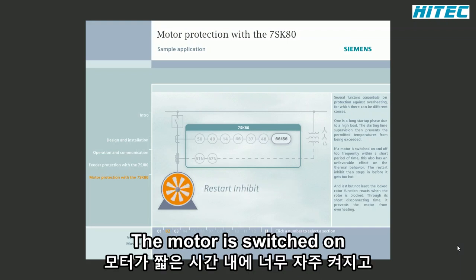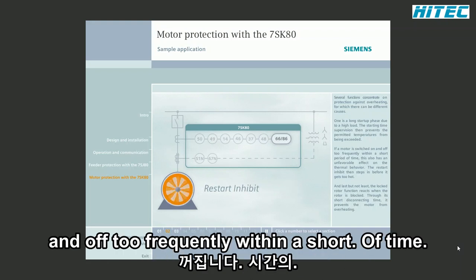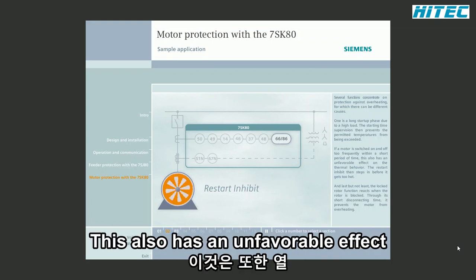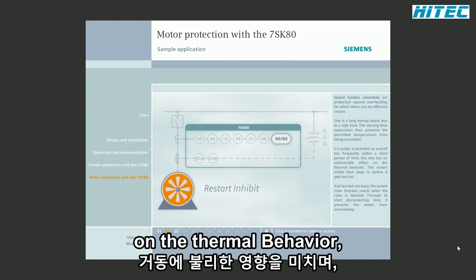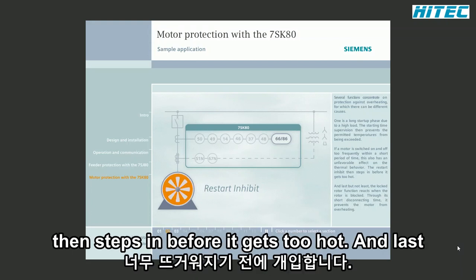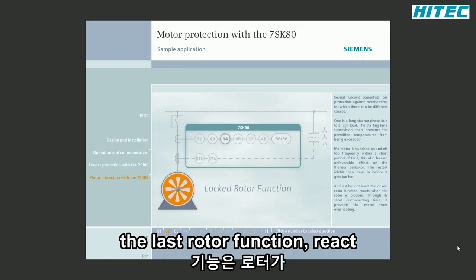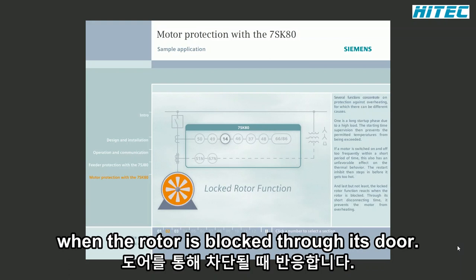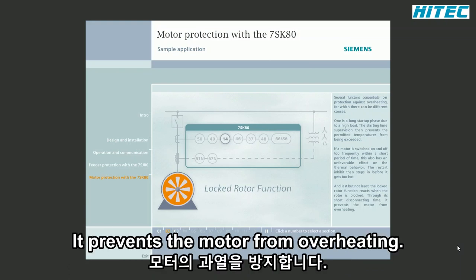If a motor is switched on and off too frequently within a short period of time, this also has an unfavorable effect on the thermal behavior. The restart inhibit then steps in before it gets too hot. And last but not least, the locked rotor function reacts when the rotor is blocked. Through its short disconnecting time, it prevents the motor from overheating.